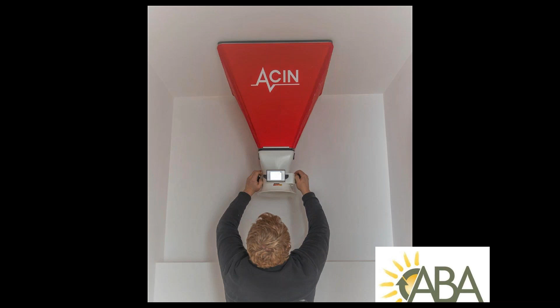Typical balancing companies are commercial companies working on very big systems. This is small, you can see that little thing in my hands there. It measures down to just a handful of CFM very, very accurately. Most of that commercial equipment isn't very accurate below 100 CFM. So be careful who balances your system.